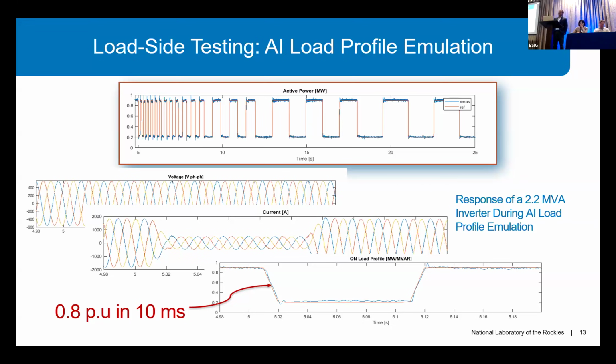So the CGI or the grid simulator is consuming this power in real time, and for this particular test, it was supplied by a 2.2 MVA inverter. So basically we are exposing the 2.2 MVA inverter to an AI load profile. And at the bottom you see high resolution measurements showing 3-phase voltages and 3-phase currents during one of the particular steps of AI load fluctuation. In terms of the ramp rate, we can go from 0 to full power of several megawatts within 4 or 5 milliseconds.